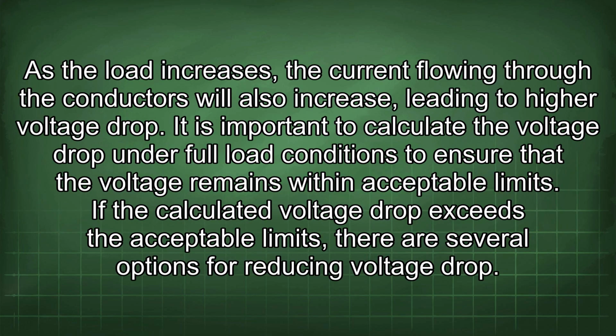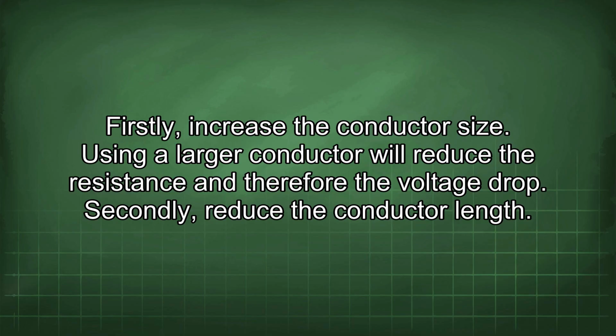As the load increases, the current flowing through the conductors will also increase, leading to higher voltage drop. It is important to calculate the voltage drop under full load conditions to ensure that the voltage remains within acceptable limits. If the calculated voltage drop exceeds the acceptable limits, there are several options for reducing voltage drop. Firstly, increase the conductor size. Using a larger conductor will reduce the resistance and therefore the voltage drop.